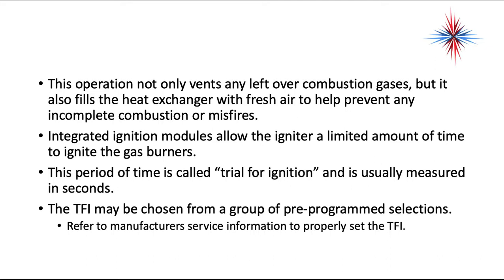Integrated ignition modules allow the igniter a limited amount of time to ignite the burners. This period of time is called trial for ignition and is usually measured in seconds. The trial for ignition may be chosen from a group of pre-programmed selections. You always want to refer to the manufacturer's service information to properly set this time.